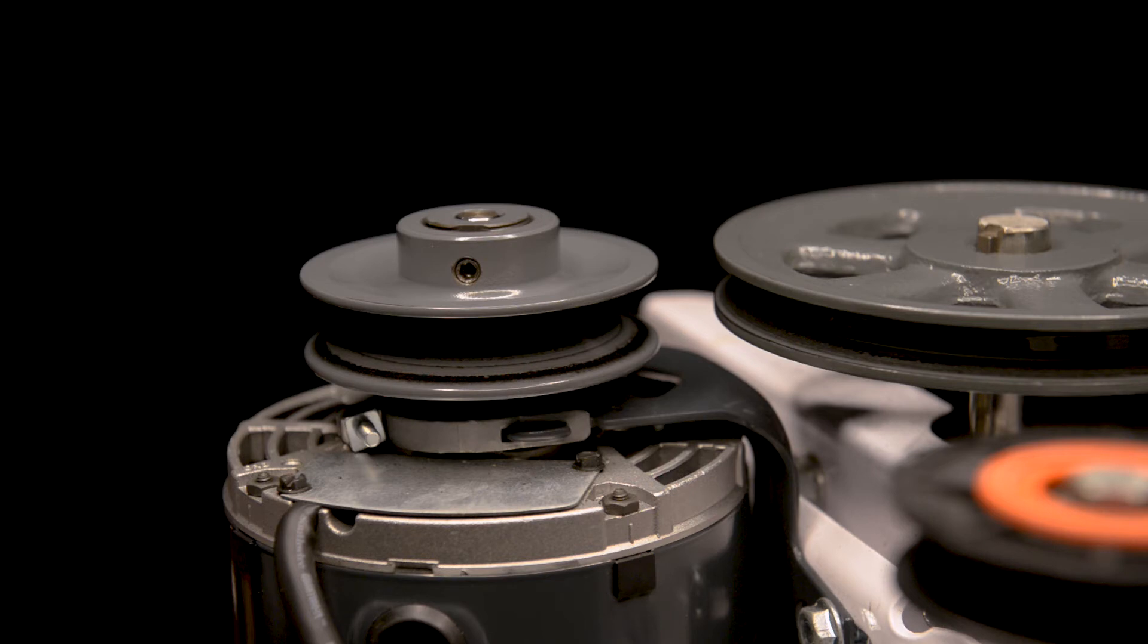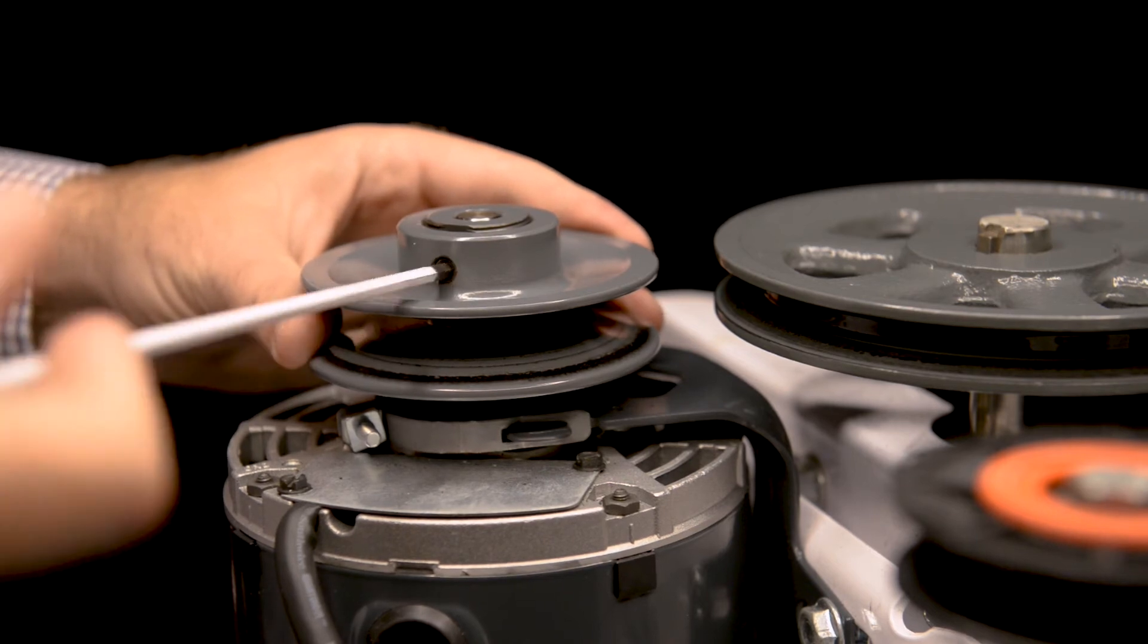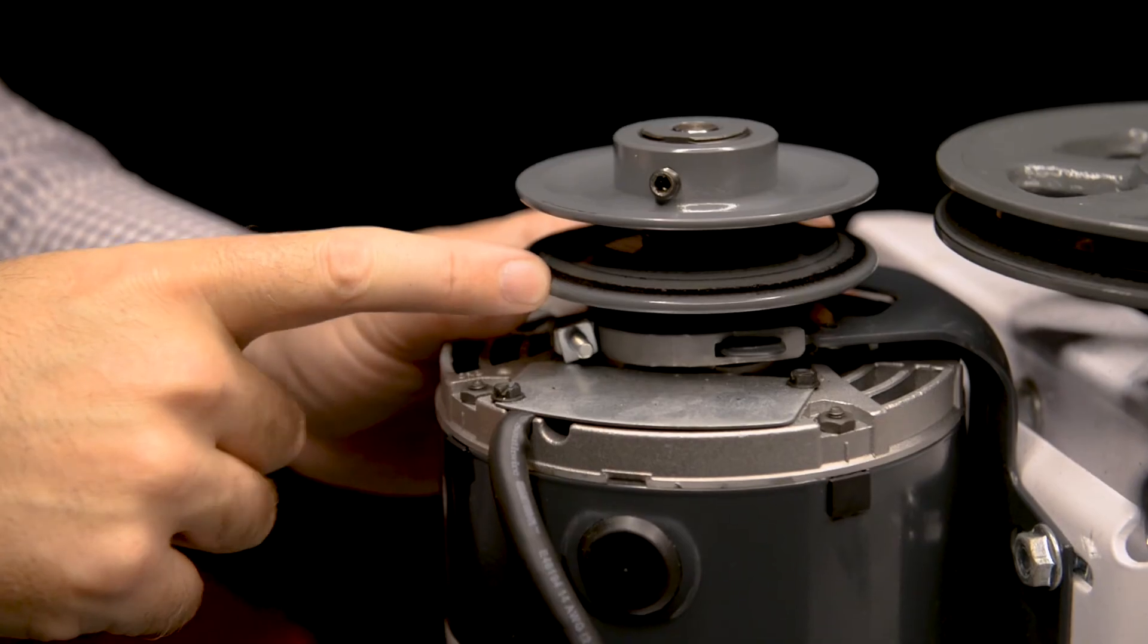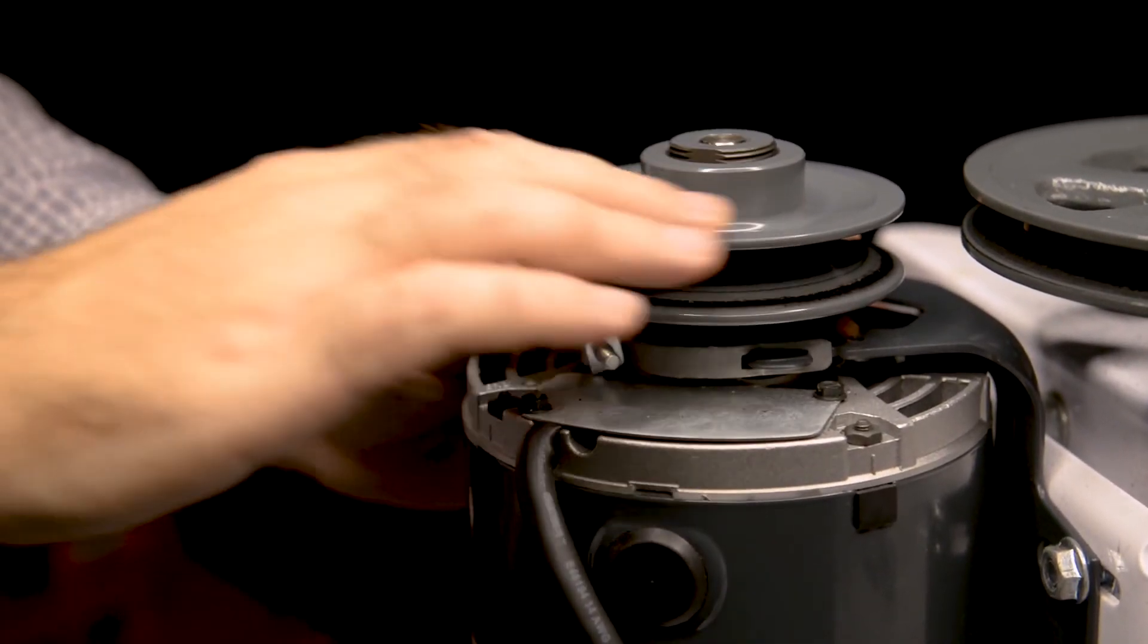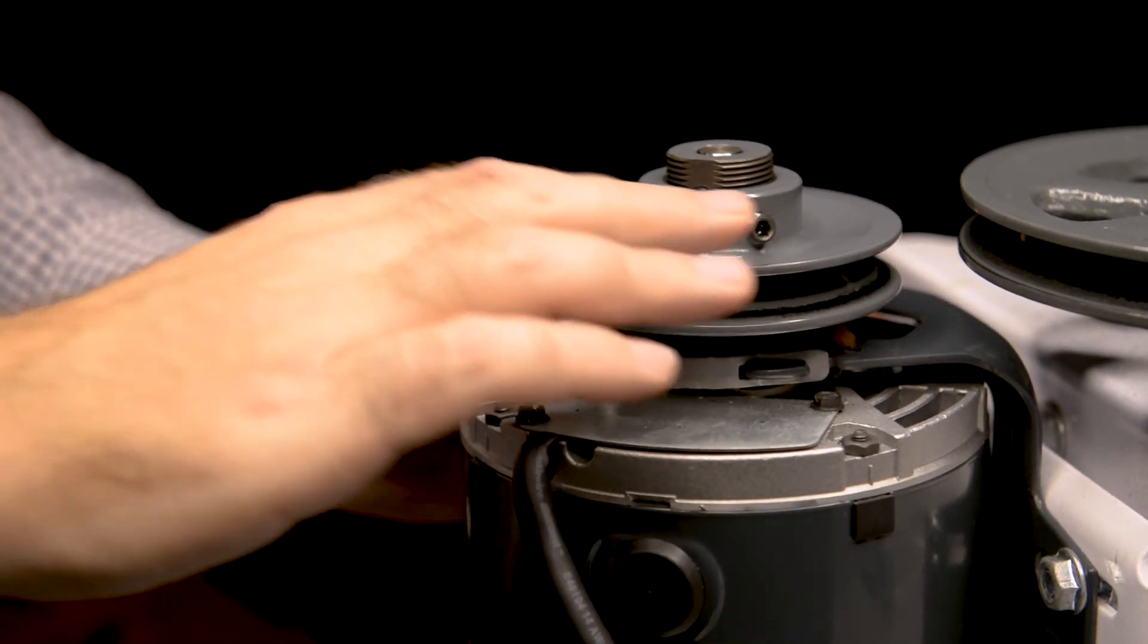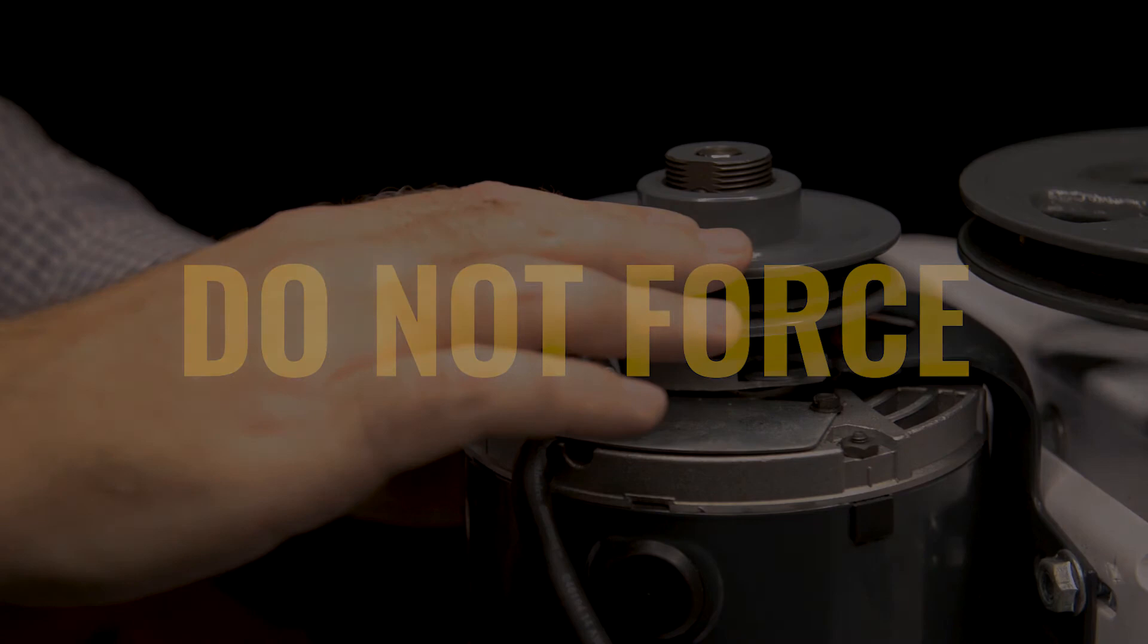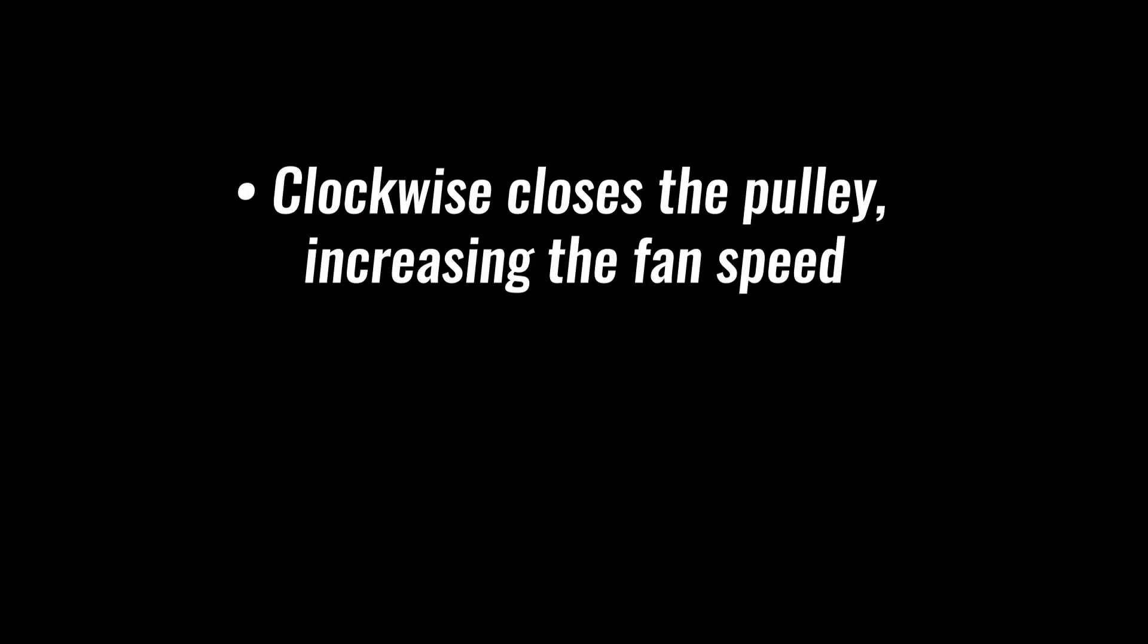To adjust the effective diameter of the pulley, locate the set screw on the top of the pulley. Using the correct size hex key or allen wrench, loosen but do not remove the set screw. To adjust the pulley, hold the bottom half of the pulley with one hand while turning the top half of the pulley. Do not force the pulley. If the top half of the pulley does not turn freely, then the sheave may be damaged and will need to be replaced.